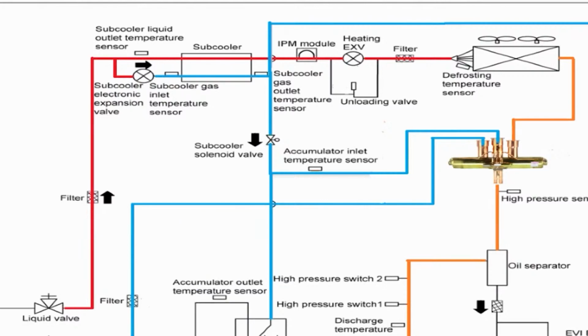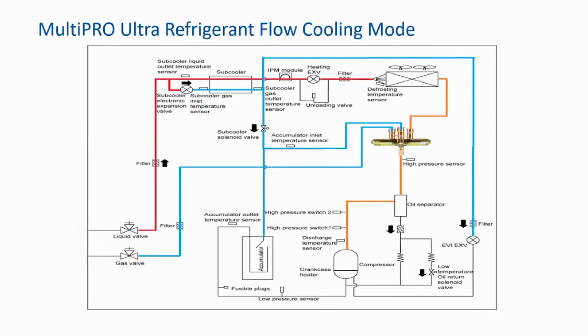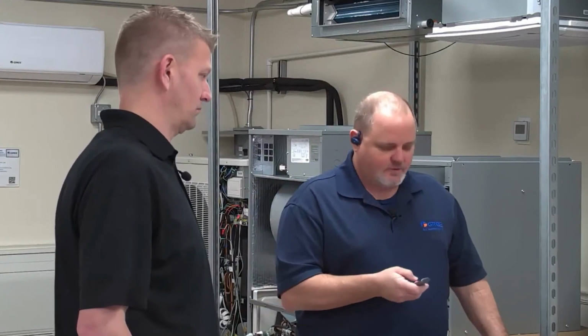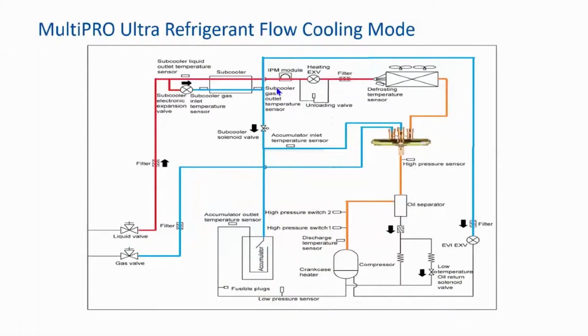And on the service tool, is that just to take the load off of the compressor or the unit itself, or is it to get your liquid temperature down so we get a better flash point at our indoor EEV? Okay. So again, that's going to be dependent upon other load conditions within the machine that our outdoor board is constantly looking at. All the thermistors and stuff like that, just like we talked about in the mini split yesterday. It's constantly digesting all of the data that it's getting to know what the machine needs to do.